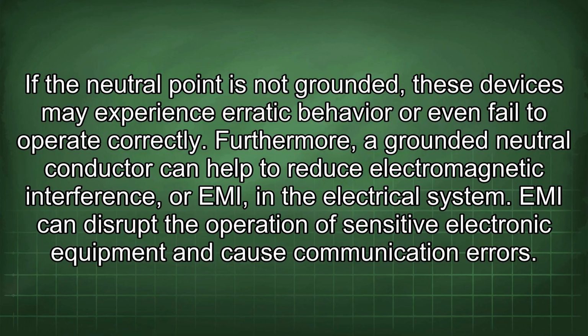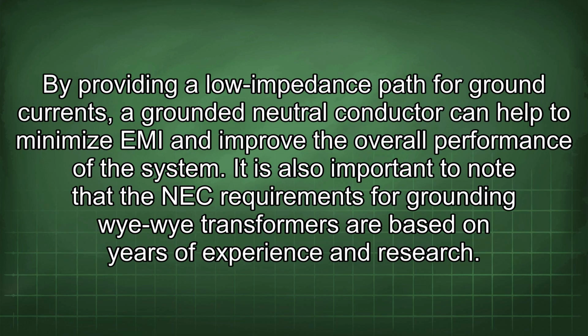Furthermore, a grounded neutral conductor can help to reduce electromagnetic interference, or EMI, in the electrical system. EMI can disrupt the operation of sensitive electronic equipment and cause communication errors. By providing a low impedance path for ground currents, a grounded neutral conductor can help to minimize EMI and improve the overall performance of the system.